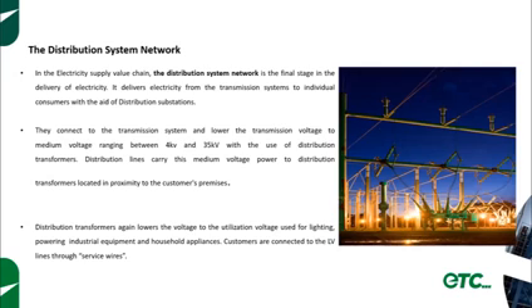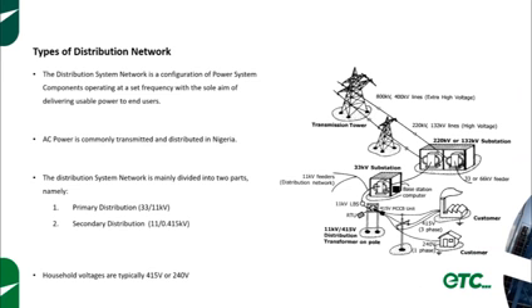We have two parts of the distribution network: primary and secondary. Primary distribution covers power from injection substations down to distribution transformers. Secondary distribution covers power from distribution transformers down to customers' service wires and load points.